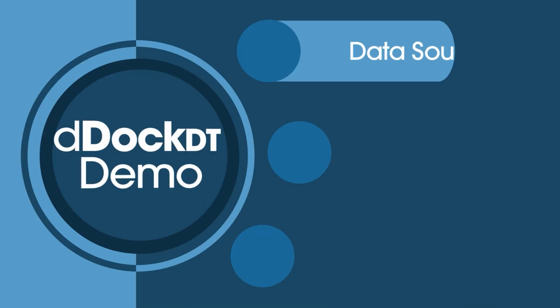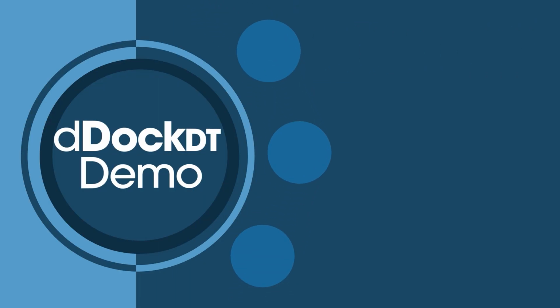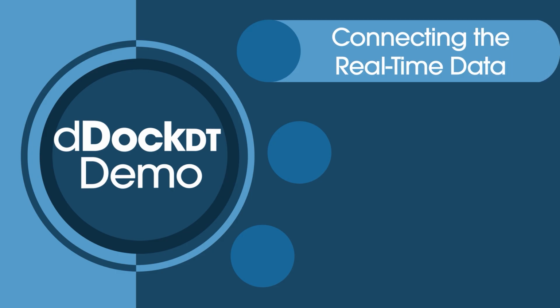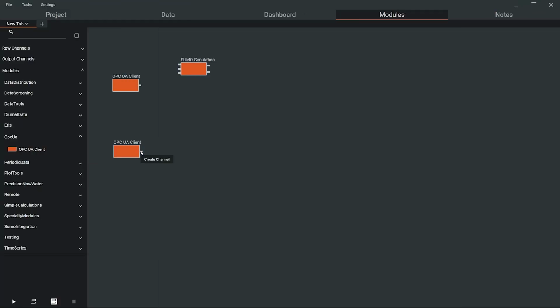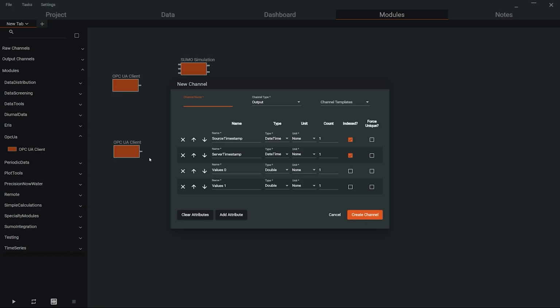The fourth step in this process is to connect this real-time data to a data flow scheme. Because the OPC client in dDock is accessing data locations in a data stream from the OPC server, it is good practice when multiple variables are being accessed to assign the incoming data to a channel with appropriately labeled attributes. In this case, the second OPC client is accessing the effluent ammonia and effluent nitrate, so we will create a channel with those names in the appropriate entry fields.